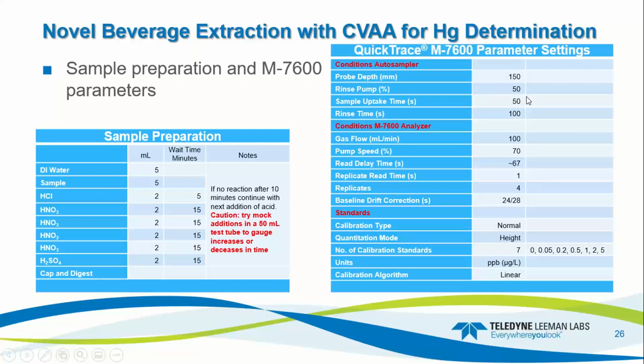My pump rate on the auto sampler was 50%. Uptake time for the sampling was 50 seconds. Rinse time was 100 seconds. Gas flow was 100 milliliters per minute. As I mentioned earlier, the pump speed was 70. My read delay time was approximately 67, 1 replicate times 4. Baseline correction was 24 to 28.